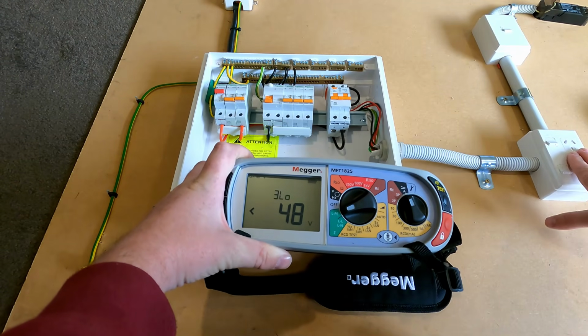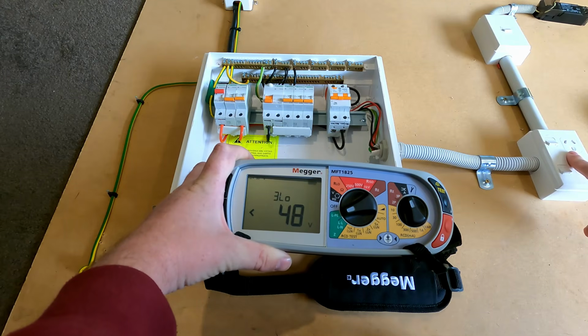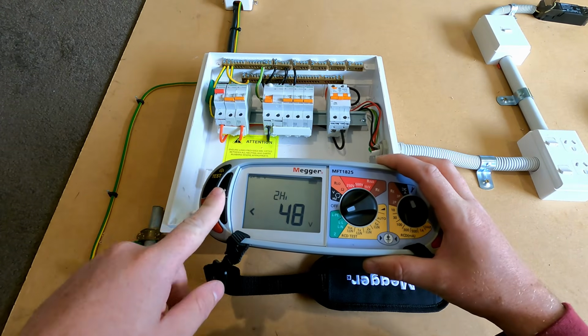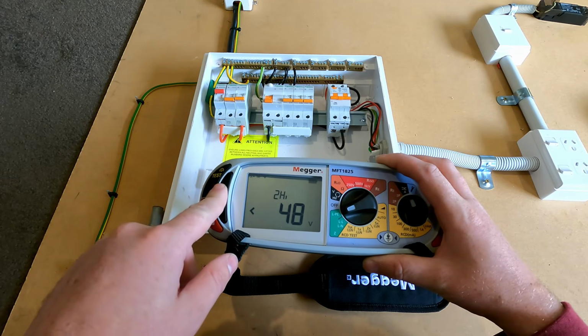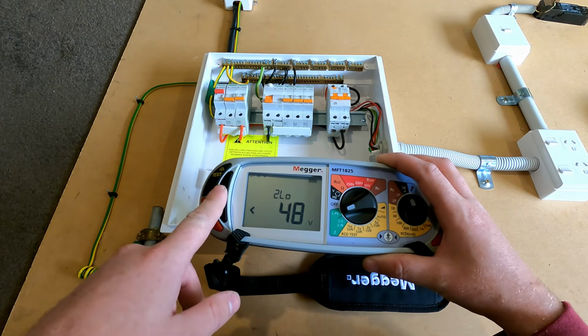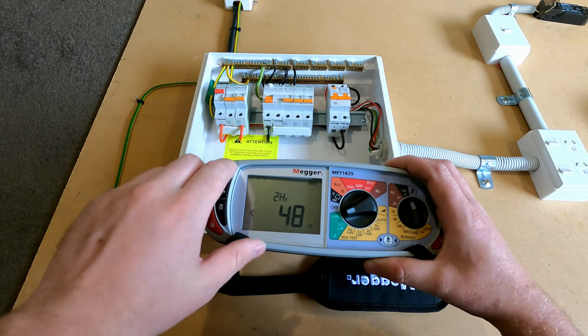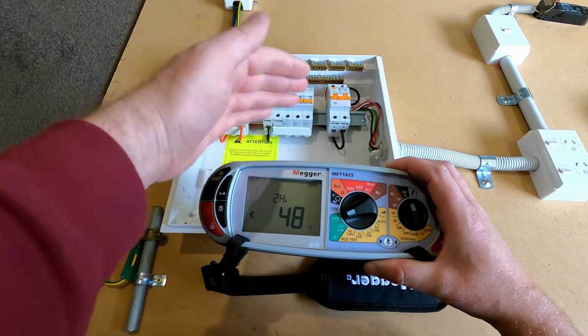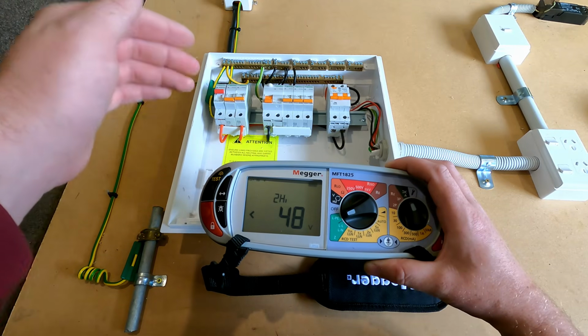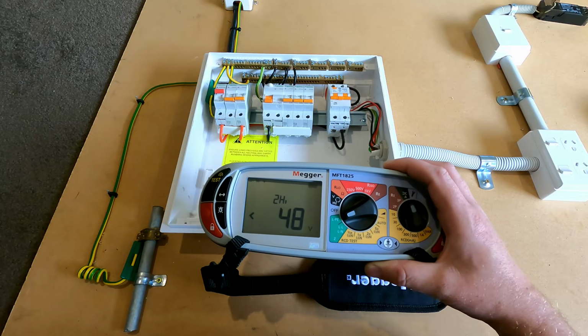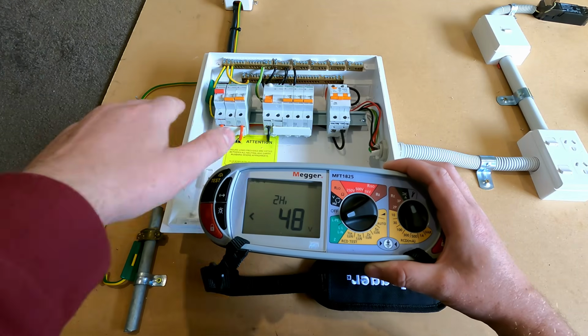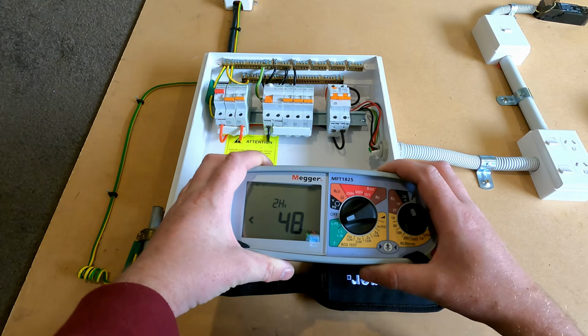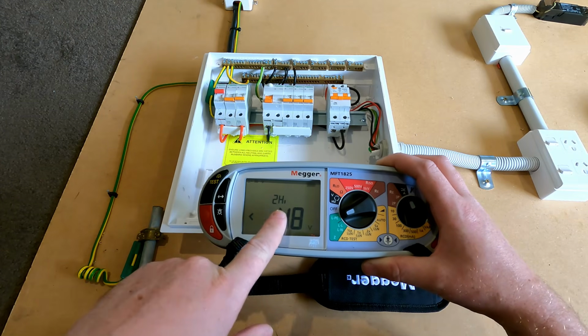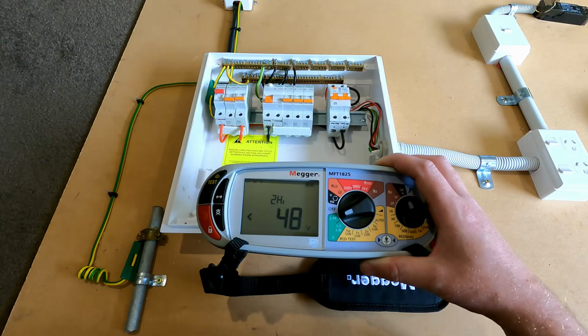So you'd use this test on the load side of your RCD circuit, so on your socket circuits, and then if you push the select button here, you can go between the other 2 lead tests on here. So there's 2 high and 2 low. First of all, the 2 lead high current tests you want to do on the line side of your RCDs in the switchboard. So we're going to be testing from the line side of the main switch to ensure that if there was a short circuit, all of the switchboard gear could stand up to the current that would be produced from it. The 2 high test is the most accurate one, but it's definitely going to trip your RCDs if you're throwing it on them, so it doesn't work.